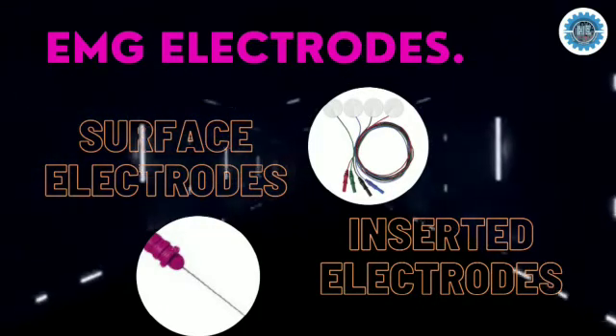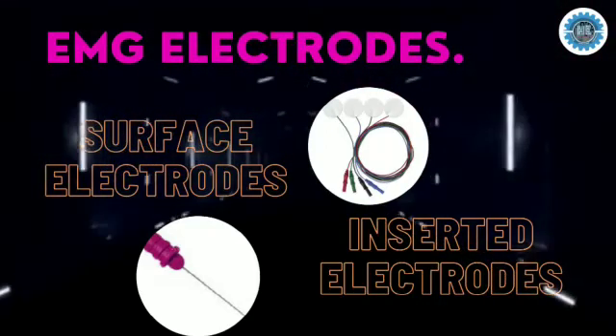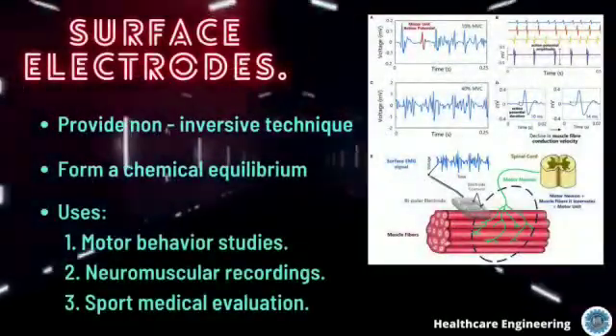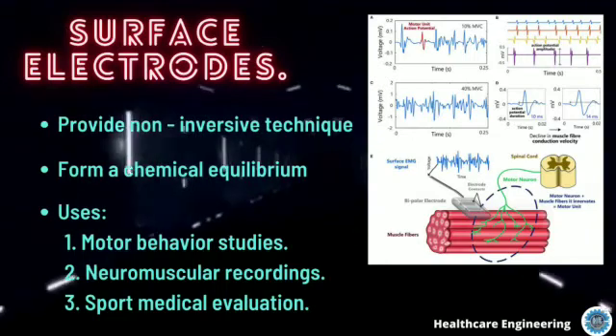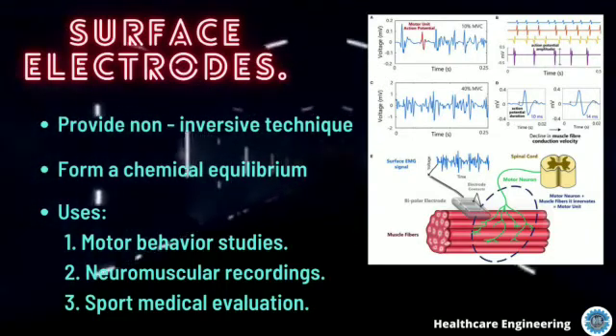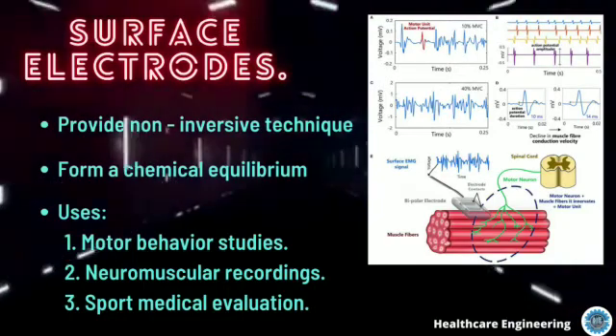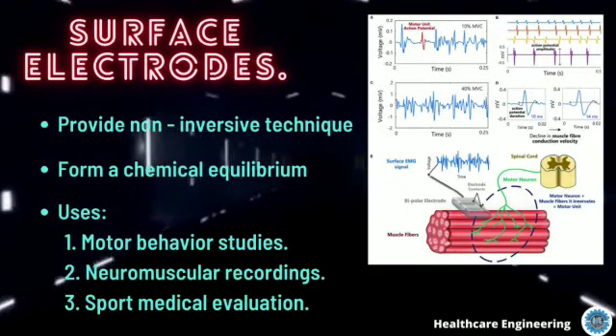Mainly, there are two types of electrodes: surface electrodes and inserted electrodes. Surface electrodes provide a non-invasive technique for measurement and detection of the EMG signal. The theory behind these electrodes is that they form a chemical equilibrium between the detecting surface and the skin of the body through electrolytic conduction, so that current can flow into the electrode.